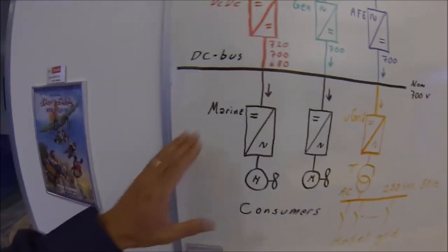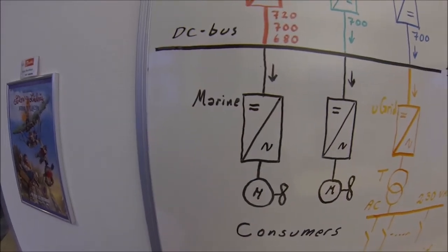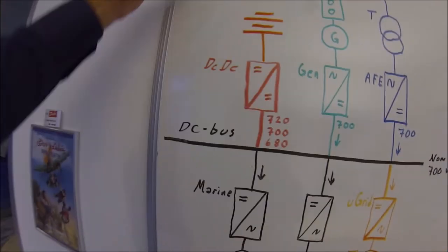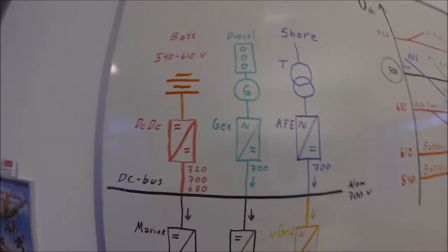When we are planning the load share on this DC bus, the consumers are pretty easy. They will be happy with any voltage between 600 volt and 800 volt they get. However, the energy sources into the system need to be some kind of synchronized to be load shared.